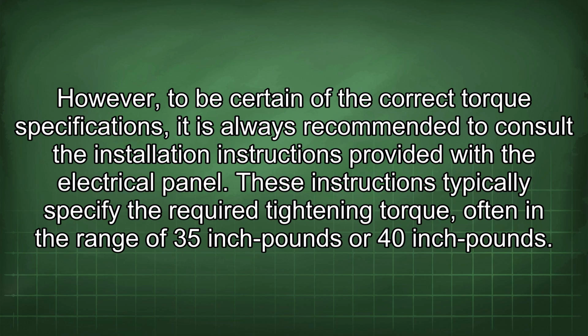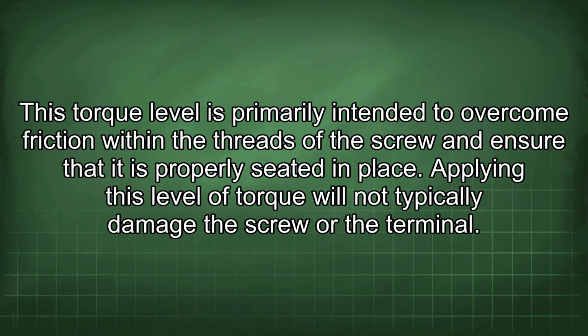However, to be certain of the correct torque specifications, it is always recommended to consult the installation instructions provided with the electrical panel. These instructions typically specify the required tightening torque, often in the range of 35 inch-pounds or 40 inch-pounds. This torque level is primarily intended to overcome friction within the threads of the screw and ensure that it is properly seated in place. Applying this level of torque will not typically damage the screw or the terminal.